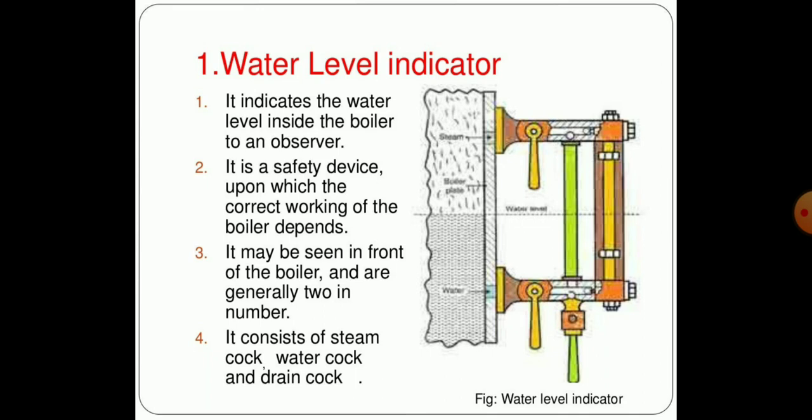First one, in front of your screen you can see the water level indicator. It indicates the water level inside the boiler to an observer. The level of water can be visible easily with the indicator. It is a safety device upon which the correct working of the boiler depends, showing the user or boiler attendant what is the level of water and it can be managed by controlling valves. It may be seen in front of the boiler and is generally two in number. It consists of steam cock, water cock, and drain cock.